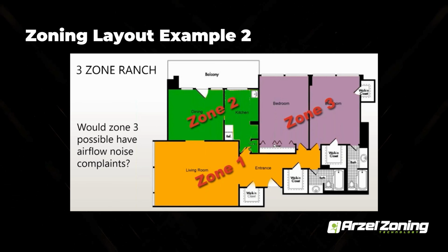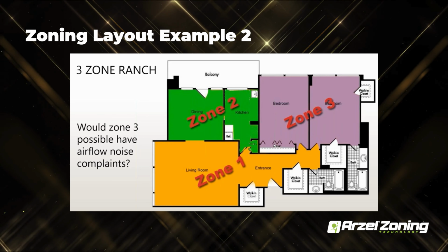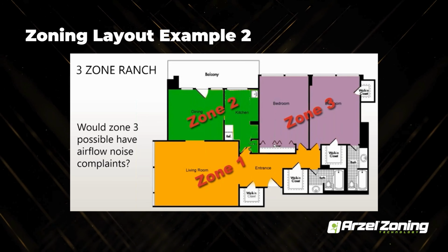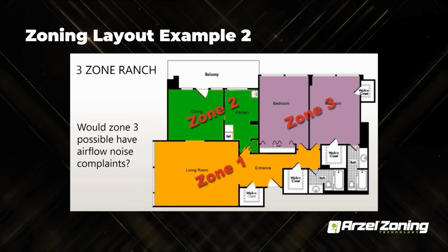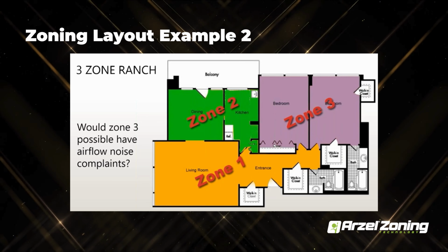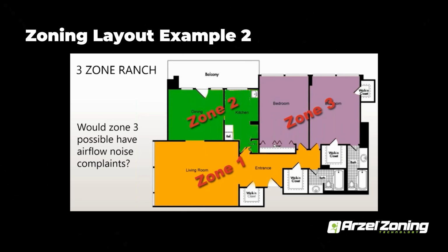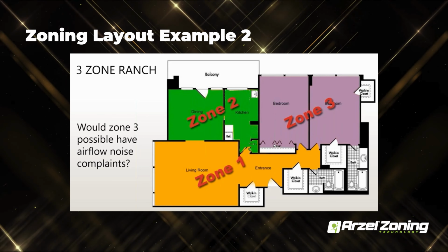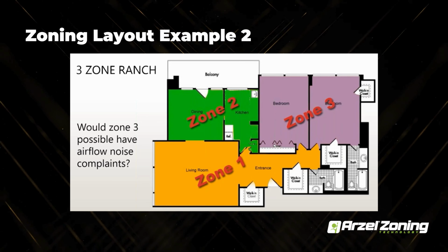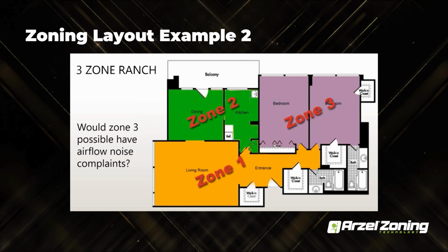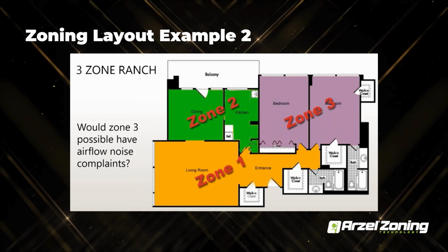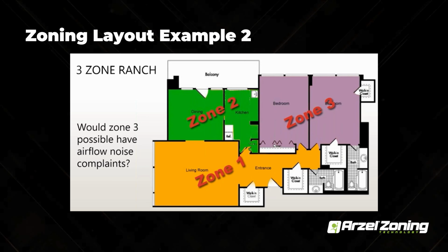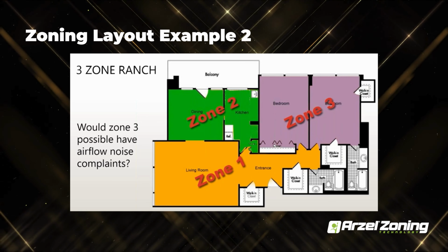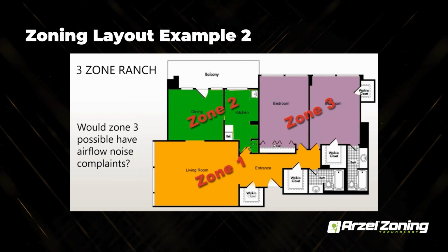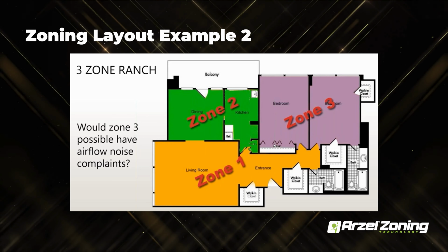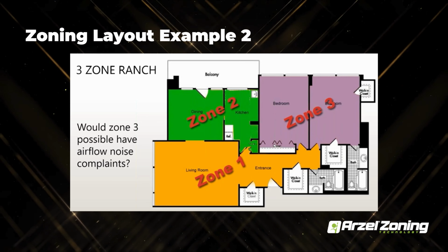So if you take a look at this example here, this is a 3 zone ranch. If you're looking at your zones, they look all somewhat even here, but do you think that zone 3 would have any kind of complaints, or possibly even zone 2 for that matter? It really depends on how many ducts you have. Say you only had 1 or 2 6-inch runs going to that bedroom in zone 3. It's really not the best possible thing to make that its own zone. A lot of times you can achieve the same thing with a slave. That way you don't have that small of CFM in that ductwork, and you're able to join that zone with any other zone before you get equipment control.